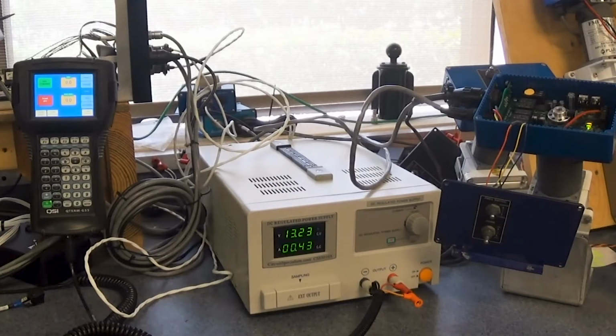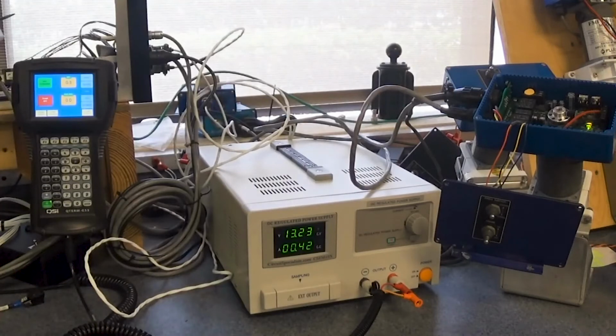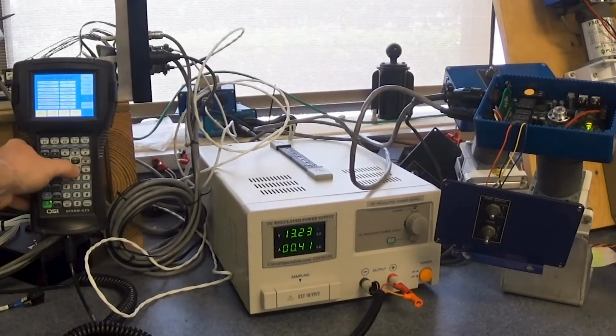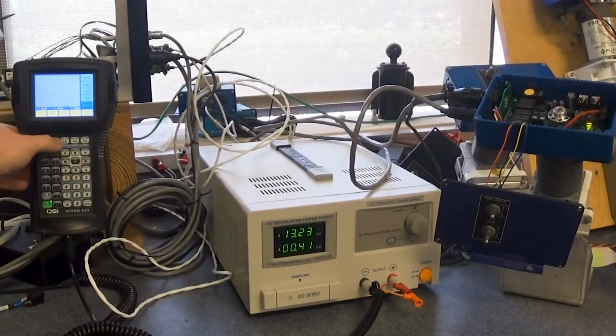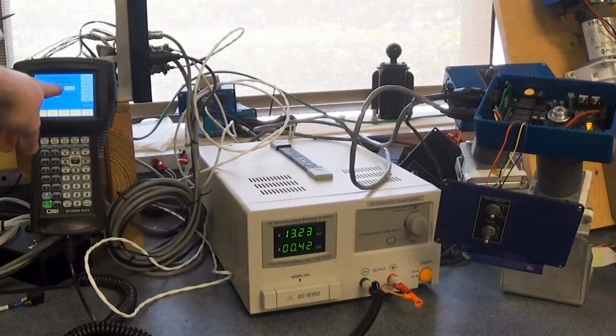However, now our problem is the calibration's no good. So once you've cleaned the sensor, you'll want to recalibrate. So we'll do that again. We'll go down to calibrate. And we'll start calibrating again. But notice what's going to happen that's going to be a bit different now. Now we have a pulse per second count for our high calibration rate. This is what we should be expecting.